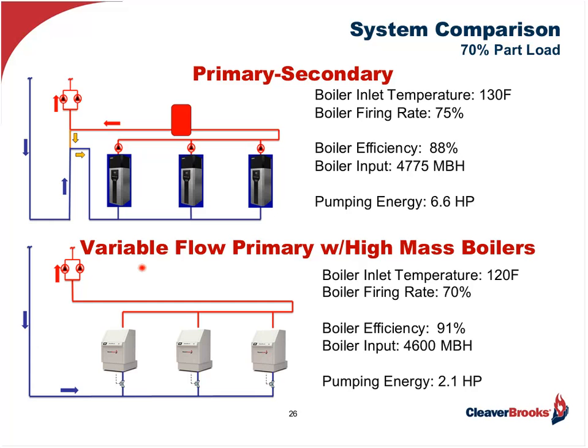Now the reason the firing rate is higher is the next line. The boiler efficiencies, because of the higher entering water temperature, the low mass boilers are at 88%. The high mass boilers are at 91%. So the low mass boilers have to work a little bit harder. And then finally, because of course the secondary pumps are throttling back and your horsepower is going to vary with your cube, the pump horsepower has dropped, at least on the system pumps. But the primary pumps are still running. So there's about a 4 horsepower pumping difference.